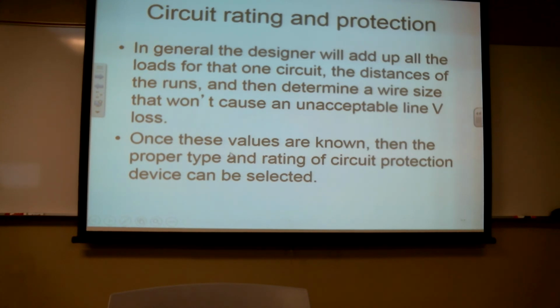So again, rely on the manufacturer's recommendations for wiring size and circuit protection, and you'll find they're way overkill. You'll read, okay, maximum is 0.72 amps, blah, blah, blah, and they say use a number 18 wire with a 4 amp circuit breaker. That's way overkill. That component will never, ever generate enough current to trip that circuit breaker.